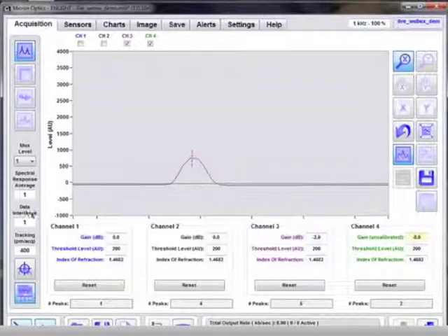On the bottom left here, you see a data interleave control. What this allows you to do, directly between the Enlight interface and the instrumentation interfaces, is reduce the rate at which data is served from the instrument. So while this is not literally changing the speed of your 1 kilohertz instrument, what it is doing is allowing the instrument to continue running at 1 kilohertz, where all of the receiver electronics have been tuned and all the calibration has been optimized, but then to reduce the data rate to whatever your needs are, which may be less than 1 kilohertz.